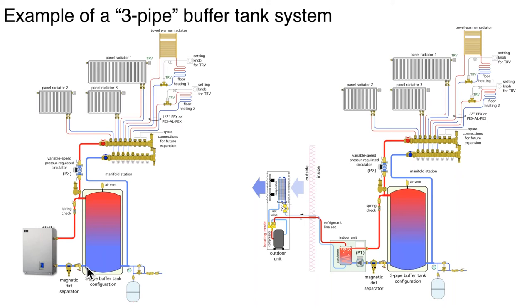It will sink and flow backwards through the heat source, dumping some of the heat that's in the thermal storage tank into the heat source. It doesn't harm anything, but it's wasting energy that you put into that buffer tank. So you need some method, and a spring check is a very simple way to do that, as opposed to a motorized valve. A motorized valve could work, but it's definitely more expensive and potentially more prone to problems over years of service compared to a simple spring-loaded check valve.